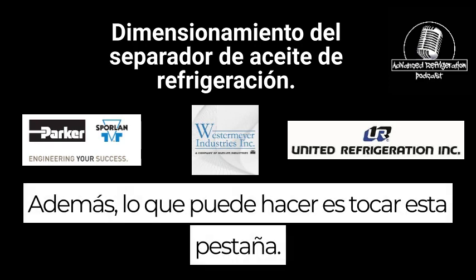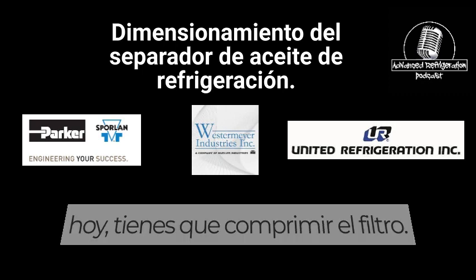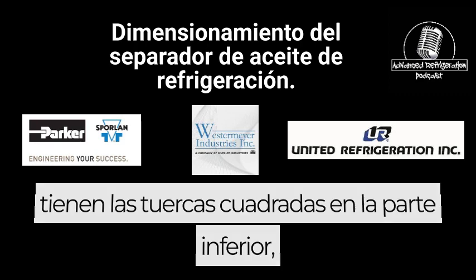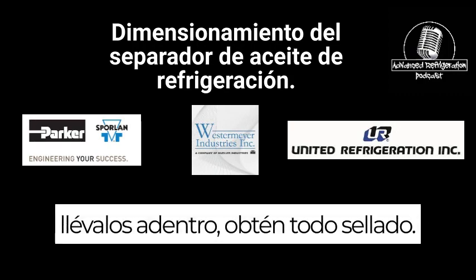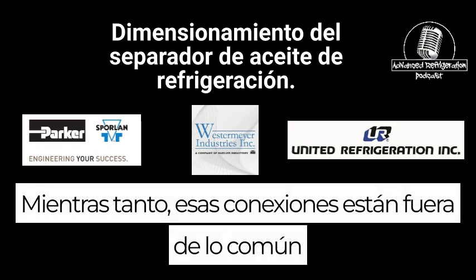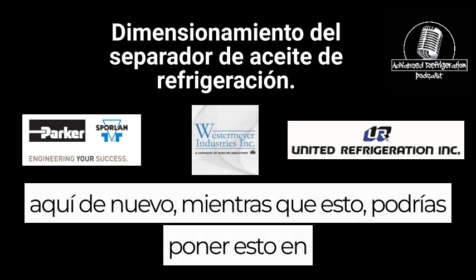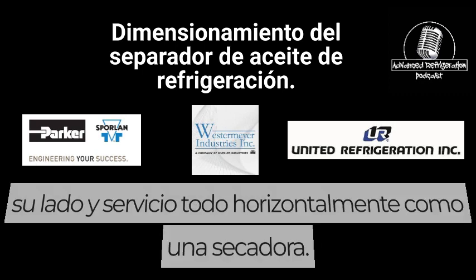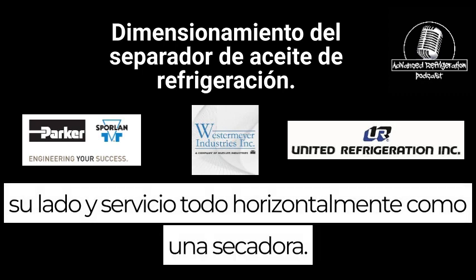Also, we've tapped this flange. So if you look at the Sporlan today, you have to compress the filter, then you have to run the bolts in, and they've got the square nuts on the bottom side, run them in, get everything sealed up. All the while, those connections are off the top here. Whereas this, you could lay on its side and service everything horizontally like a dryer.